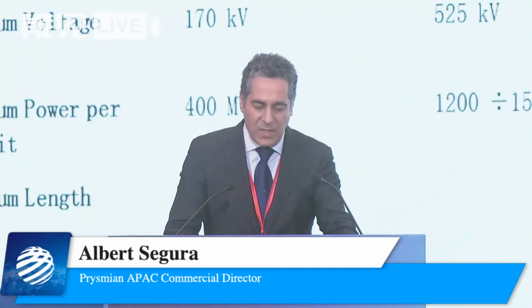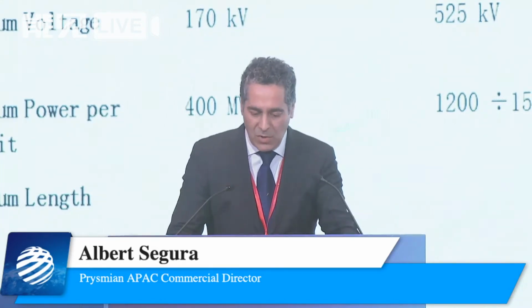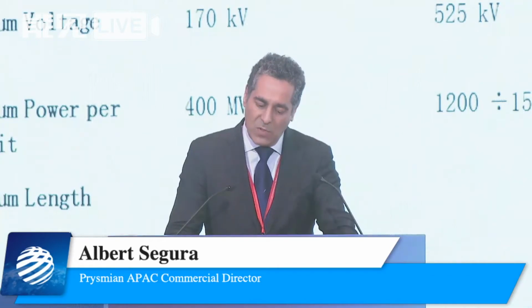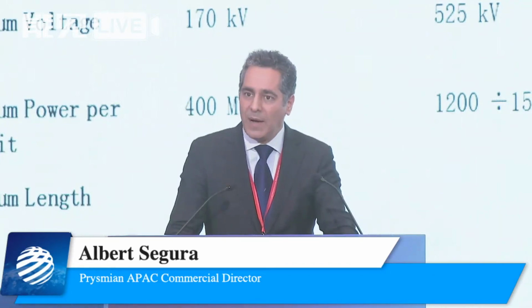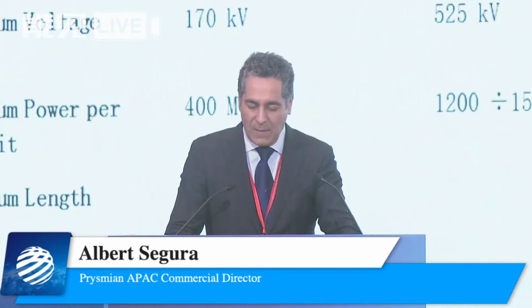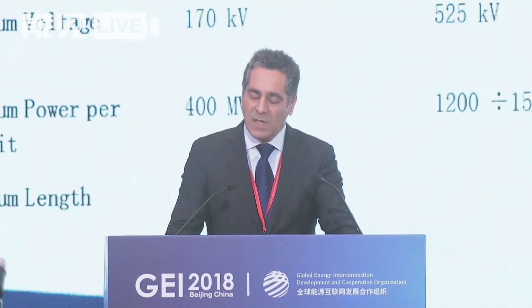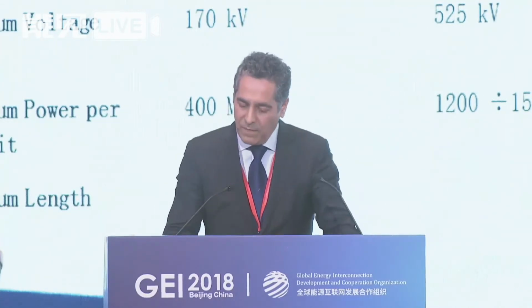In AC technology, the two on the left are land cable solutions and the four on the right are submarine cable solutions. There is EPR technology for medium voltage up to 72 kV. Three-core technology, state of the art, is 245 kV, with a three-core conductor, huge cables. Single-core conductors in XLPE go up to 420 kV. Over this voltage, we have to go with oil-filled cables.